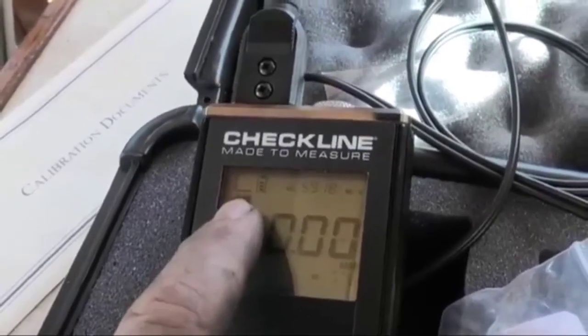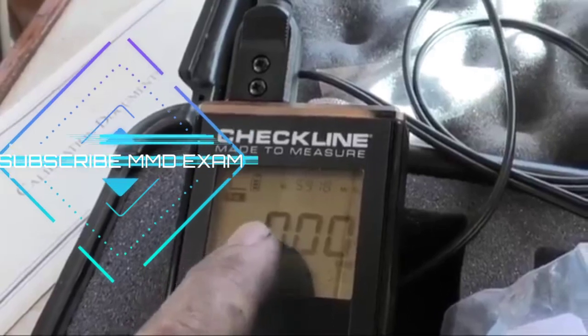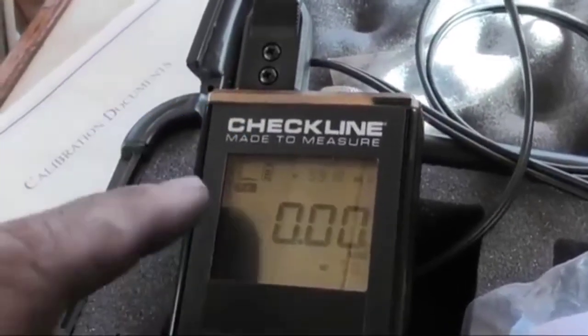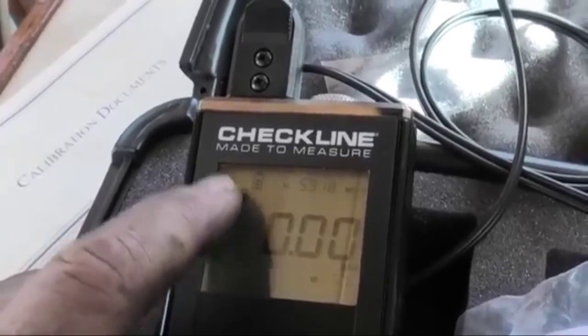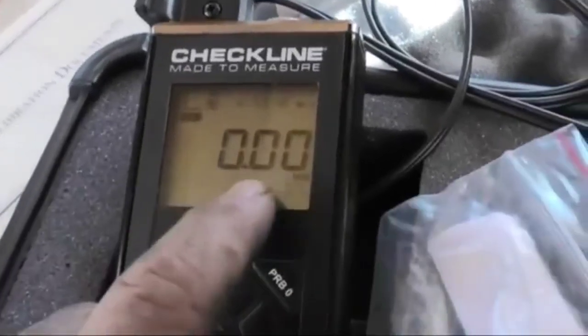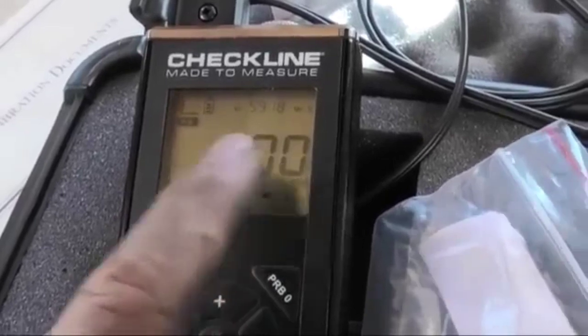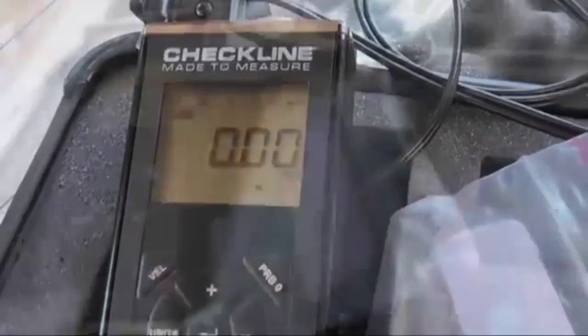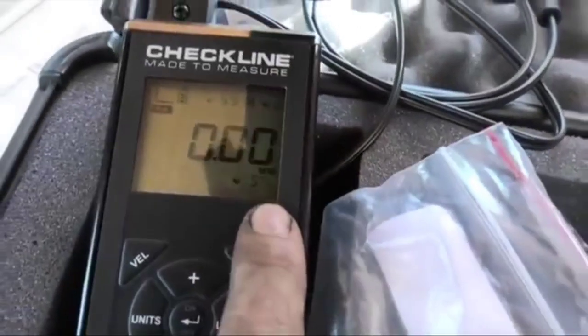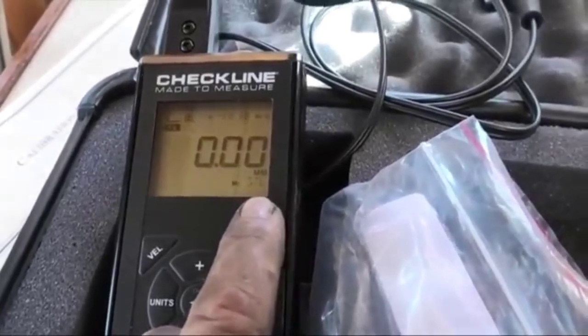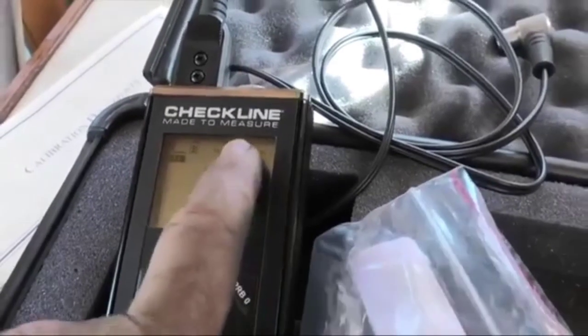If you're not getting all 6, then maybe you should have a look at what's going on, why you're getting slightly varying readings. And when I say varying readings, I'm talking like multiple times a second, it's sampling. So this is your confidence indicator. Then here, the main display is the thickness you're getting. In this case, I've got it set to millimeters. Also down the bottom here, you'll see it says STL, which is steel. So steel here and your velocity here are telling you the metal you're testing.